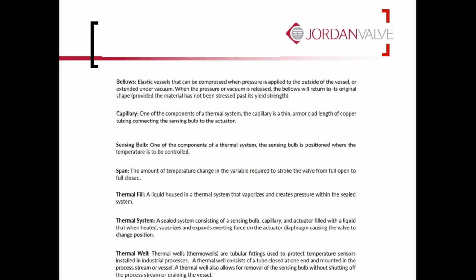Some definitions real quick. Bellows is one type of actuator design, and I'm going to go into this a little bit more later in the presentation, but the bellows will have some type of fill that expands and contracts based on temperature, and that's one type of actuator that you see out there pretty consistently. The capillary is exactly as it sounds. That's the connection between the actuator and the bulb or whatever it is that's sensing the temperature, and we'll have the fill, whatever it is that expands, contracts, vaporizes, condenses to actually move the valve. The capillary connects both of those parts.